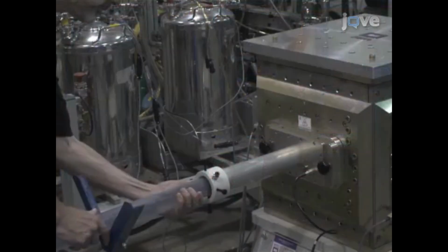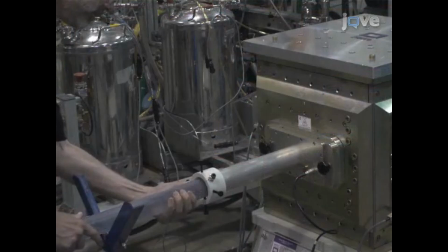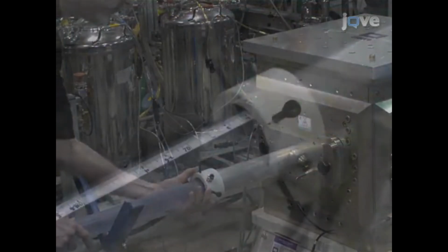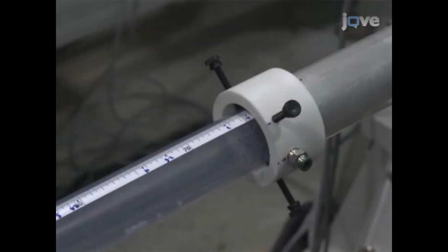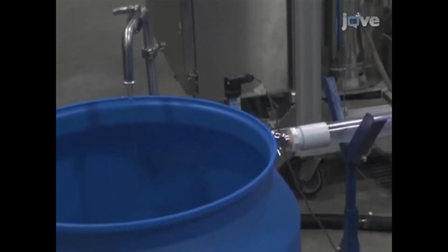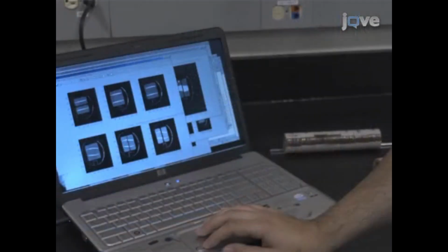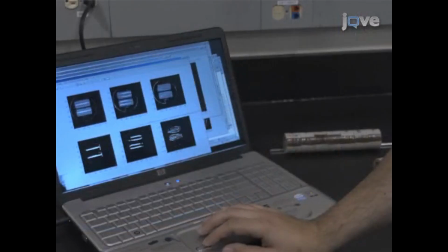Reposition the mixer to image the volumes at different axial locations. Slide the mixer tube axially through the magnet until the desired volume is at the center of the NMR coil in the center of the magnet. Then repeat the imaging process. Finally, analyze the MR data with image analysis procedures to document the spatial distribution of component concentrations.